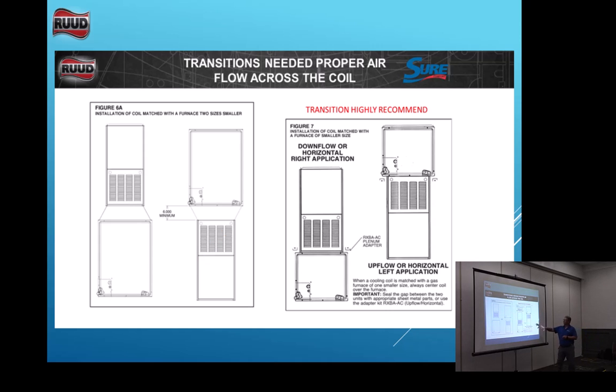If you're in the vertical or downflow position, it tells you if you have a 17-inch furnace and a 21-inch coil, you have to center that coil on the furnace. Kind of easy to do, right? You just put it in the middle and put half on this side and half on this side, right? And it's supposed to be okay.